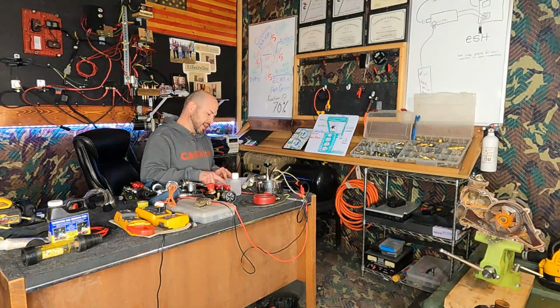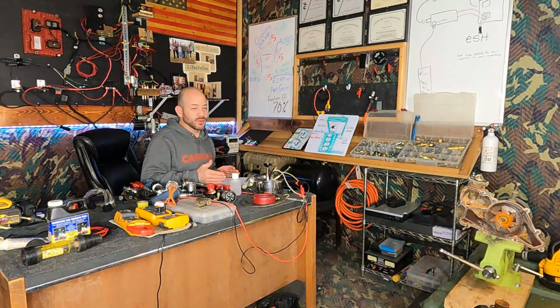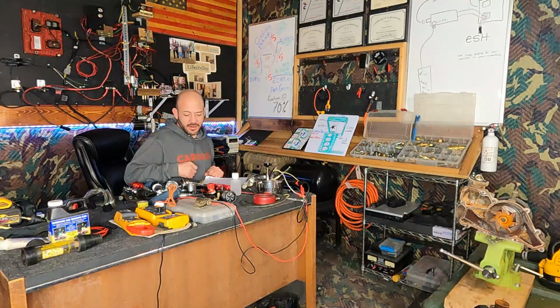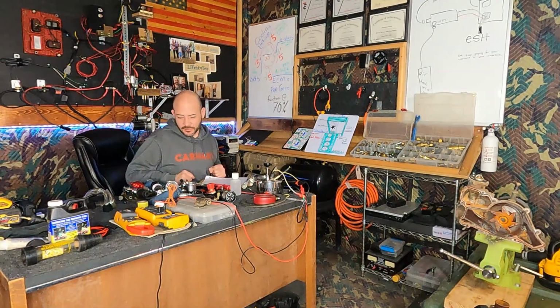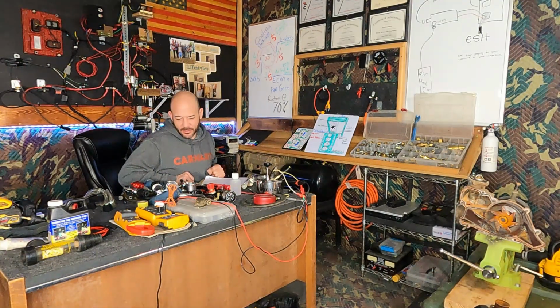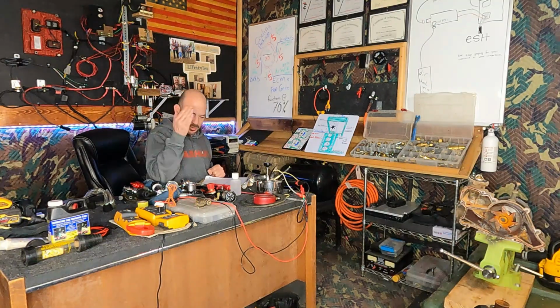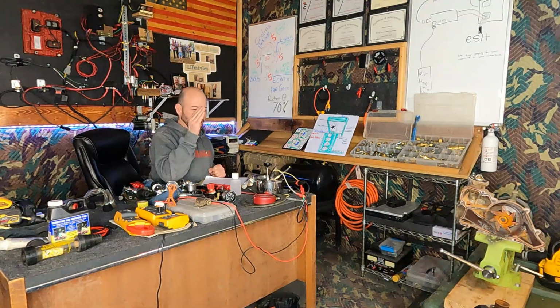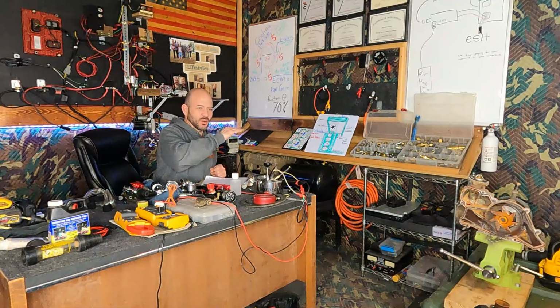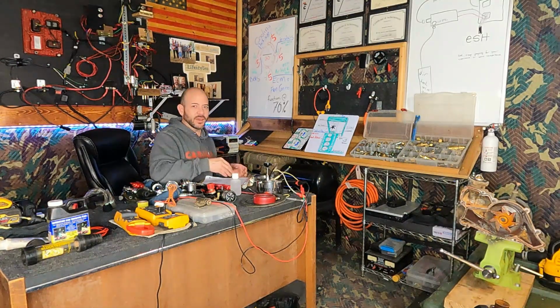A failed cap will usually still hold some pressure. They have a pressure relief valve in there that's supposed to relieve pressure beyond a certain amount of pounds, but it can also relieve pressure at a lower amount if it's failed.